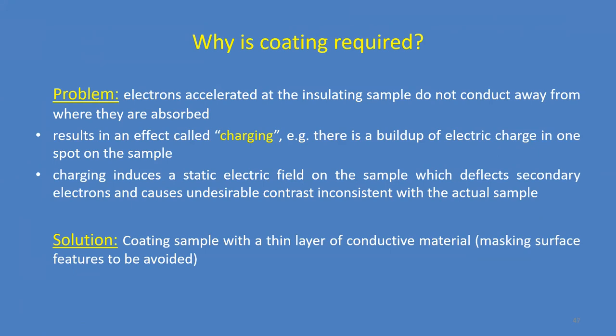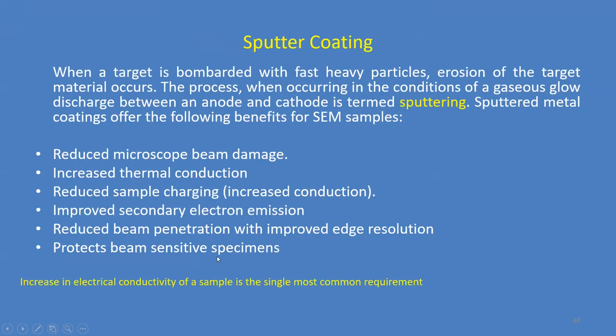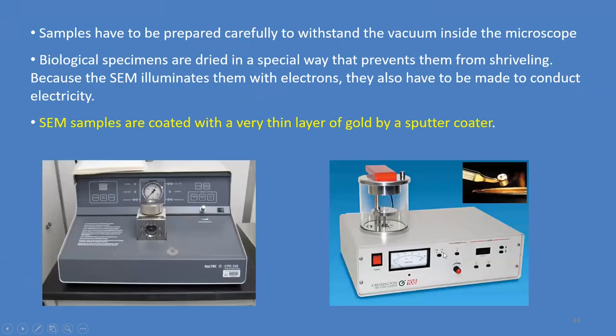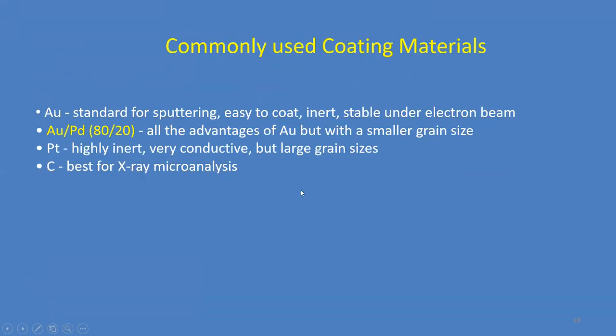And then after you do this, you have to make your samples conductive, so as to avoid this charging effect. So you have a sputter coater. The solution is to coat your specimen with a thin layer of gold. The idea is to increase the electrical conductivity of the sample so that you don't have charging effects. This is how the sputter coater looks, and this is a critical point dryer. And typically you coat with gold or gold palladium.